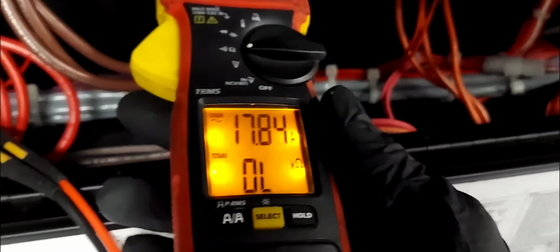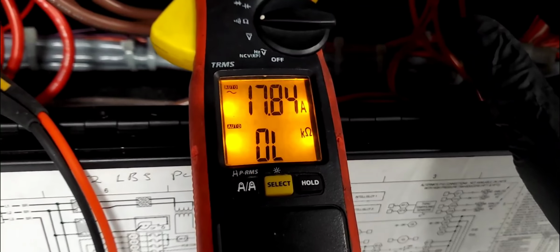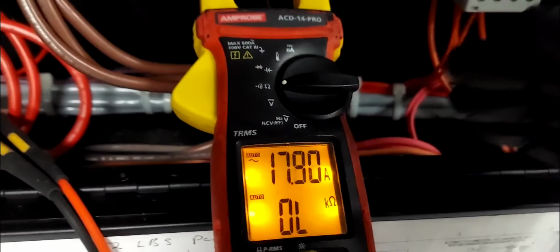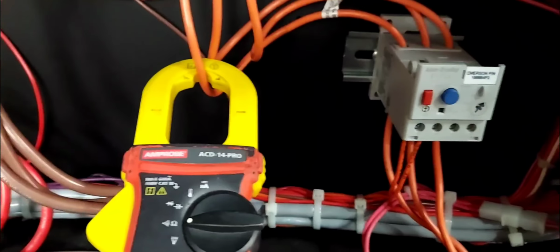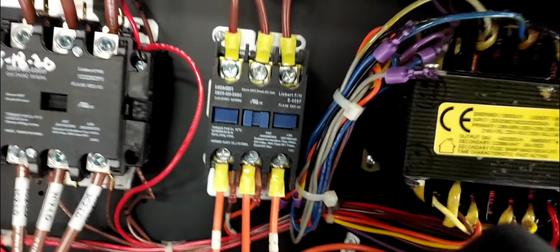I don't see why this was tripped. Either this is faulty, or the motor windings are going to be failing my mega ohm test. It passed okay with this meter to ground. However, it may not pass with the mega ohm meter. And actually, I know that the voltage coming in has to be good, because if there's an imbalance in voltage, more than likely I'd have blown a fuse. So in addition to replacing this overload, I'm going to replace the main fan contactor as well. Okay, that's going to be my recommendation.